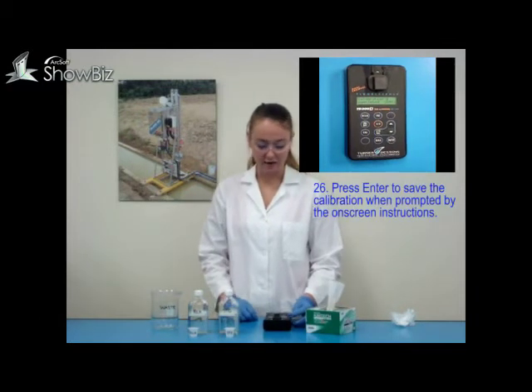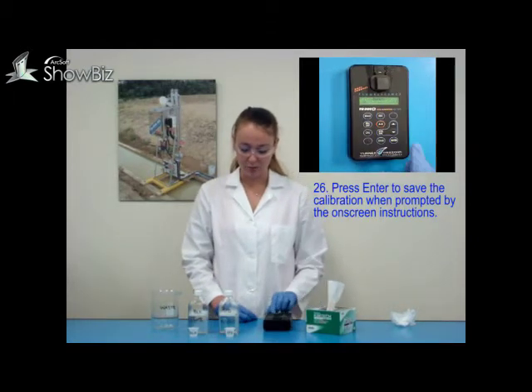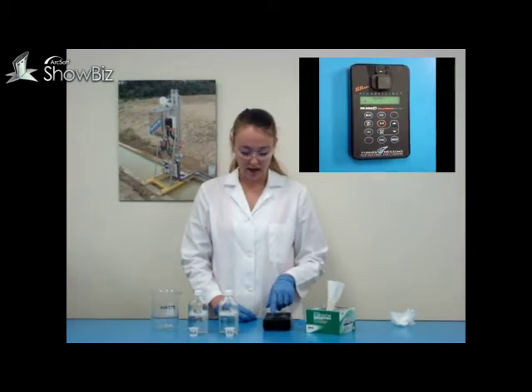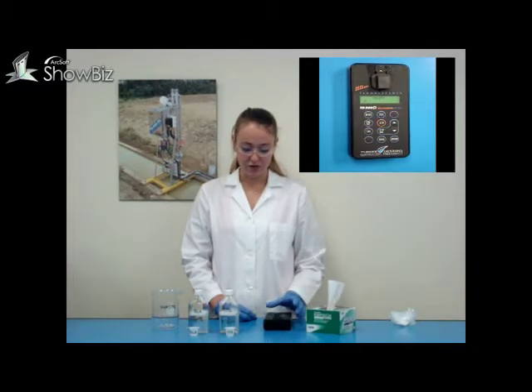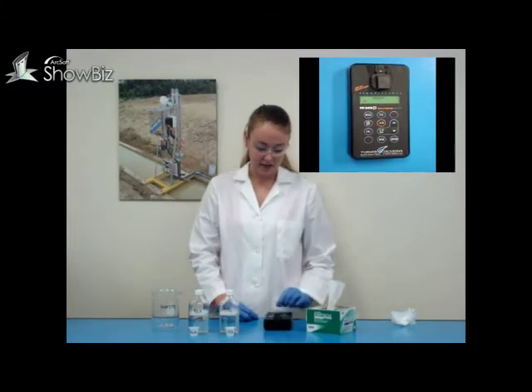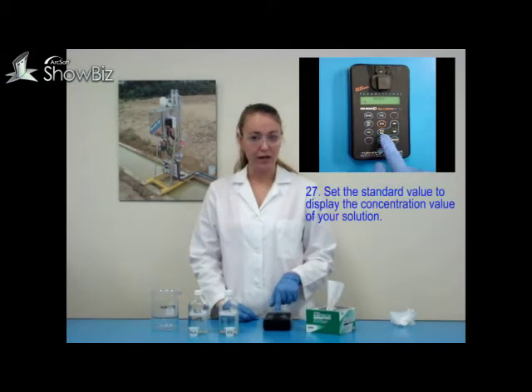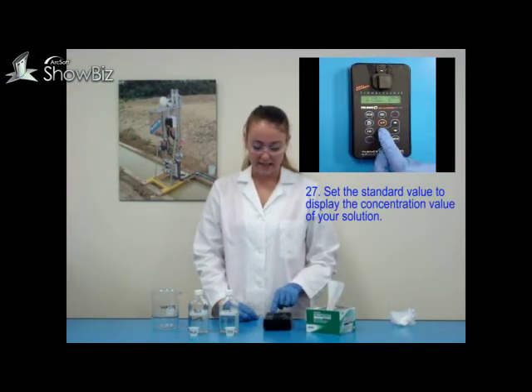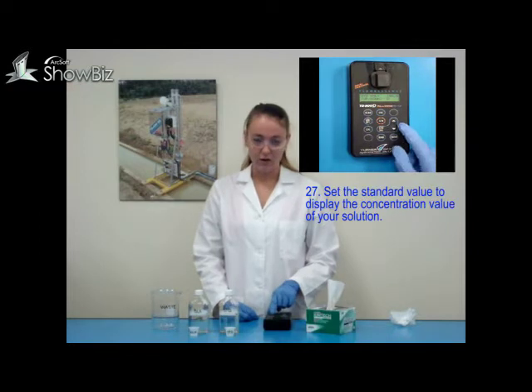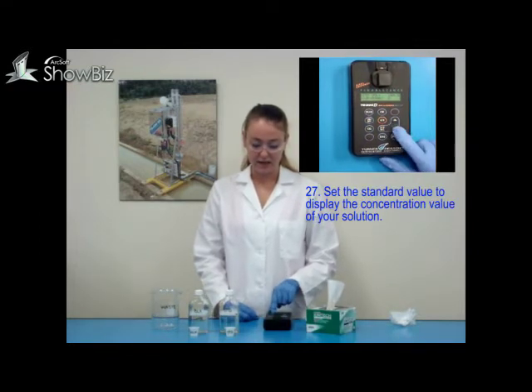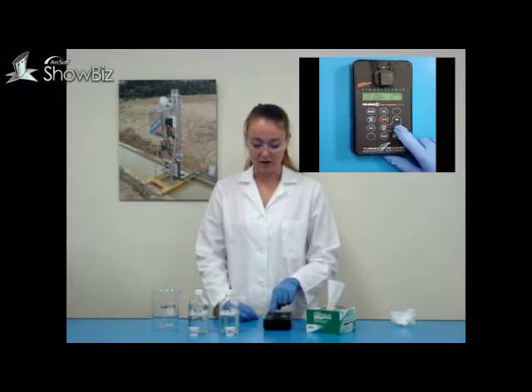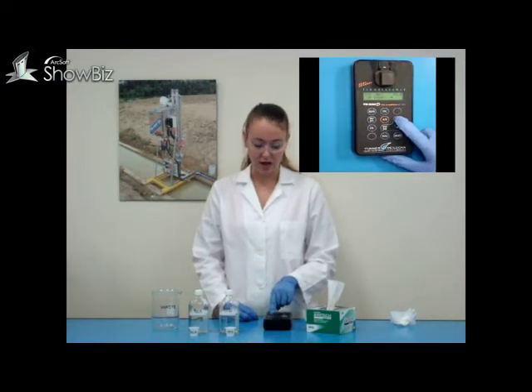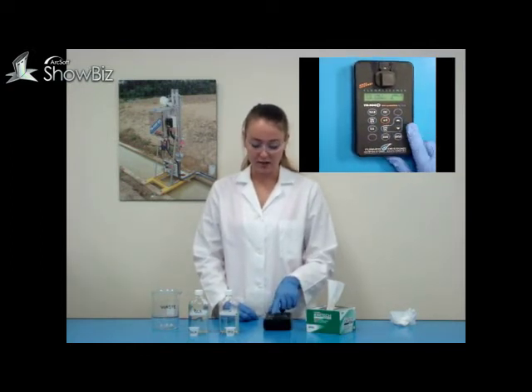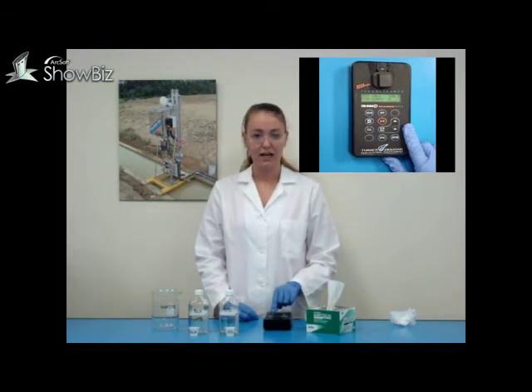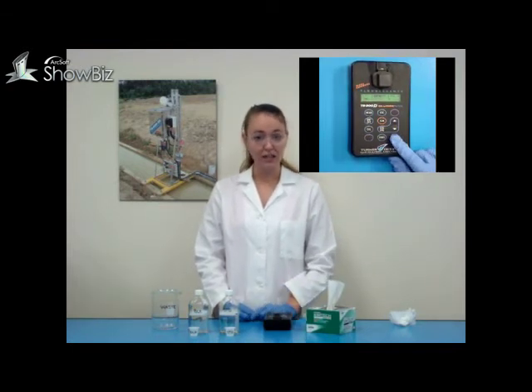The TD-500D now says calibration A completed. Press enter. You only have one last step to do to calibrate the TD-500D. You will need to press the standard value button on the instrument and set the standard value to display what concentration your solution is by pressing either the up or down arrow. In this case, our solution is 100 ppm, so we will set our standard value to 100 and then press enter. Your instrument has now been calibrated for no solvent oil and water measurement.